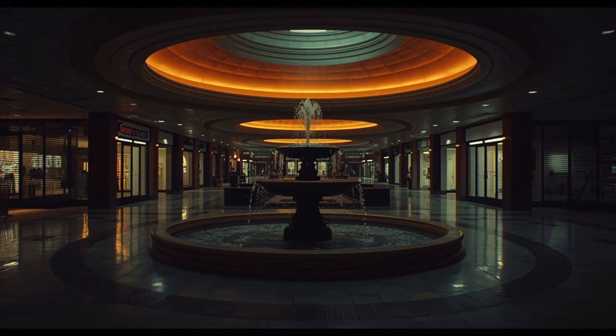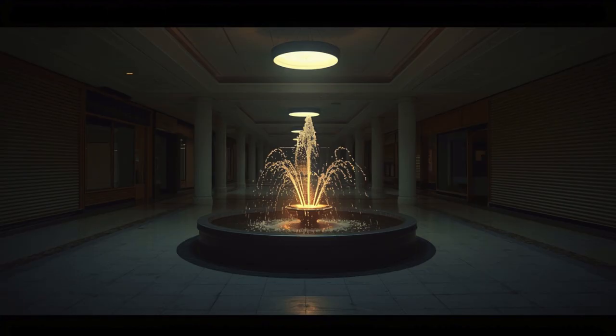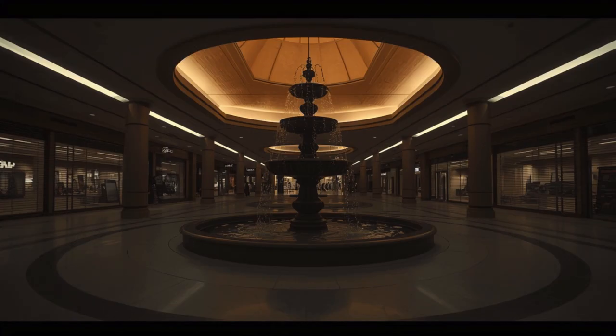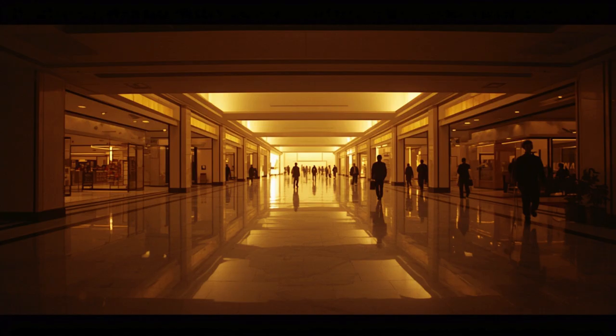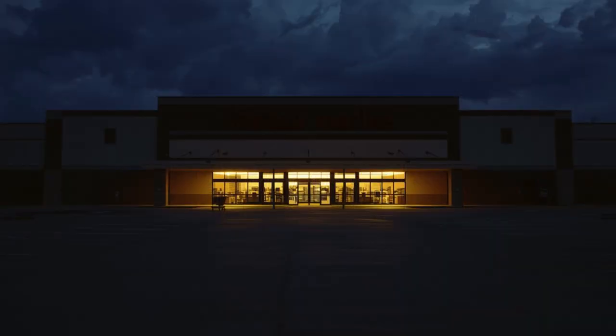The fundamental principle of mall atrium smoke control was the creation of what engineers called a smoke reservoir, a strategy in which the rising plume of smoke from a fire was allowed to accumulate in the upper portion of the atrium volume, above the heads of occupants on the surrounding floors, while the lower portion of the space remained relatively clear of smoke for long enough to allow evacuation to proceed. Achieving this required overcoming the natural tendency of smoke to spread laterally as well as upward, to spill over balcony edges and spread into the corridor spaces of upper floors, and to do so actively, using mechanical ventilation rather than relying on passive physical barriers.